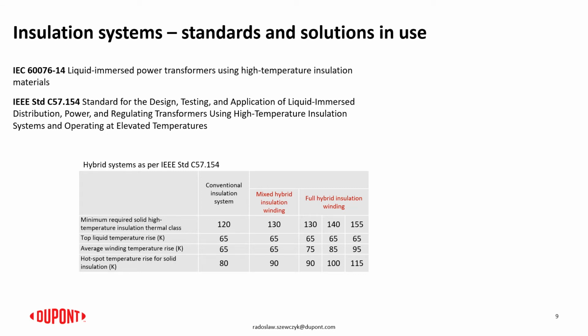And when we talk about the alternative insulation systems allowing higher operating temperature, we have those systems covered in the international standards, whether we talk about the IEC, and here is the standard 60076 part 14, or the equivalent IEEE standard C57.154. These standards define the applicability and the construction of different insulation systems using the high temperature materials like Nomex, and they also provide the guidance on the temperature limits.